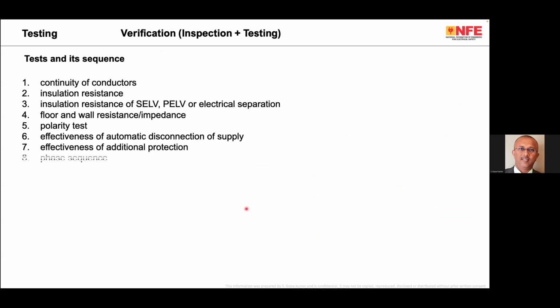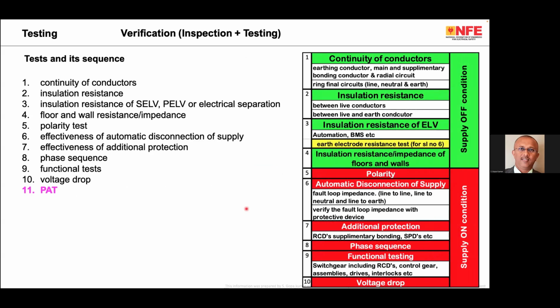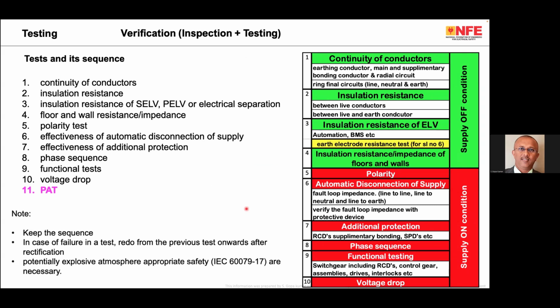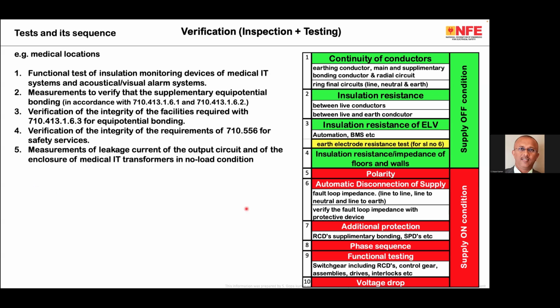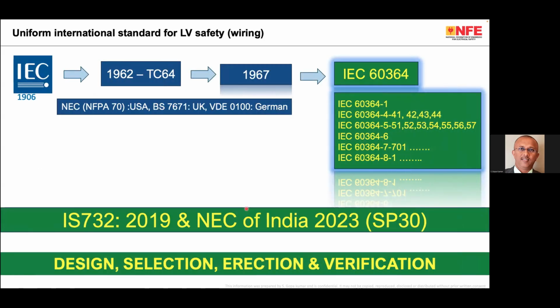After inspection, different testings are also recommended in the standard. For a normal location, for example, there are 10 testings, starting with continuity of conductors up to voltage drop. Of course, PAT is not for the installation, that is for an appliance. This is the recommended testing for a normal installation. For special installations, such as a medical location or a swimming pool or a bathroom, you need additional safety measures, and those additional safety measures need additional verification in place. You have to have an additional inspection as well as additional testing. Those inspection and testing ensure that the recommended safety measures are in compliance with the standard.